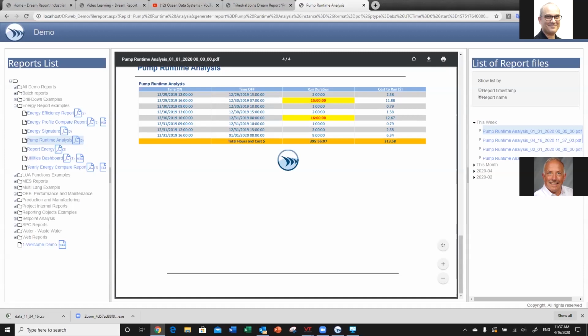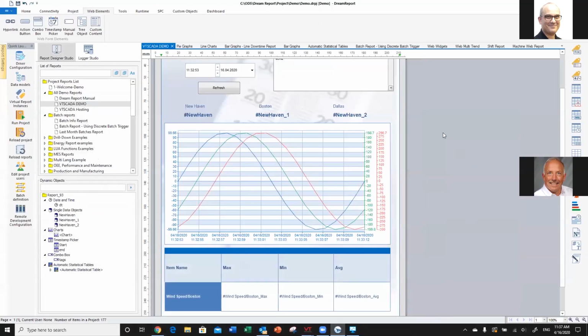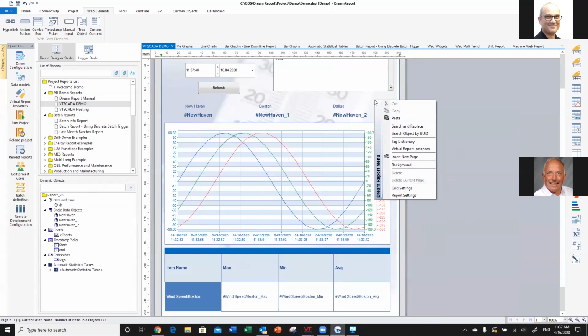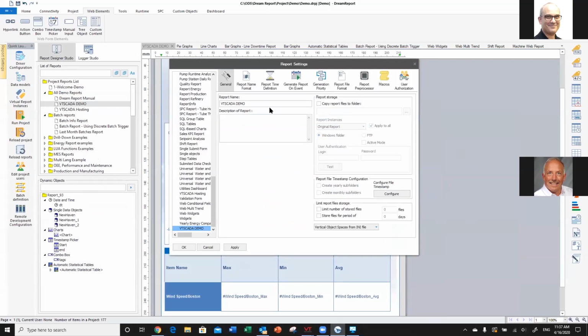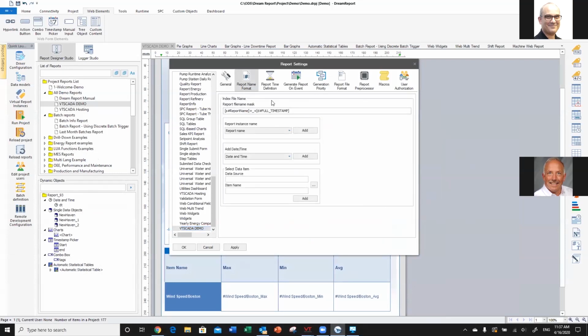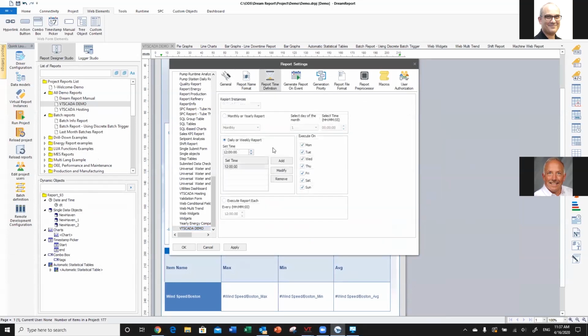Dream Report scheduling is done under what we call report settings. I can right click on the report, go to report settings, and we have file naming conventions and report triggers. If I want this report to be generated at 8 o'clock every morning except Saturday and Sunday, I've just modified the time-based schedule for the report. It could be yearly, quarterly, monthly, or daily reports. You can report on things every few minutes.